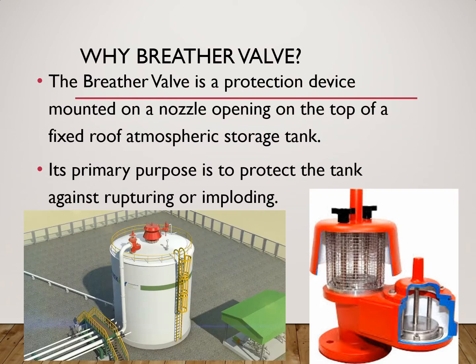Why are breather valves installed? The breather valve is a protection device mounted on a nozzle opening on the top of a fixed roof atmospheric storage tank. Its primary purpose is to protect the tank against rupturing or imploding. Storage tanks consist of liquids at the bottom and vapor space above it. There is a chance of pressure build-up and vacuum in these storage tanks. Breather vents are a pressure-vacuum relief solution for safe storage tank operation.